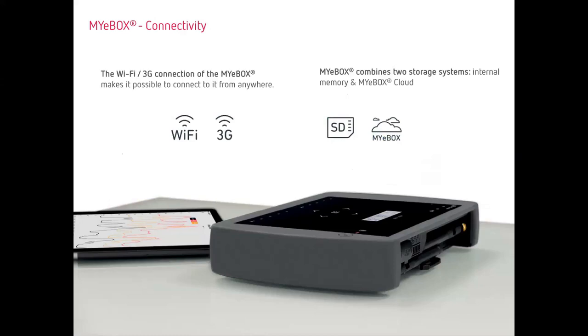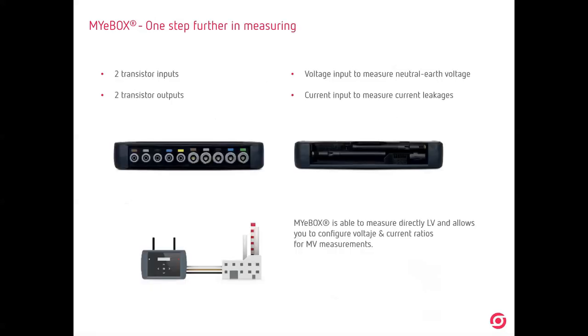Well, the connectivity of MYeBOX, as I told you, is Wi-Fi and 3G, and we have two memories: the memory inside the analyzer and the memory on the cloud. We can send the memory stored inside the analyzer to the cloud and share it with end users, with your customers. The analyzer has 5 channels of voltage and current: 3 voltages, neutral voltage, and we also measure the neutral earth voltage. The same with the current: 5 channels, 3 phases, neutral current, and residual current.